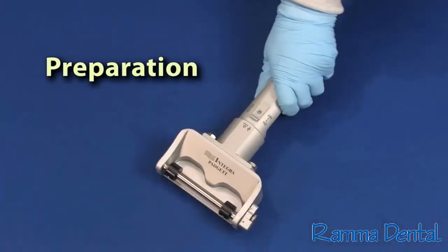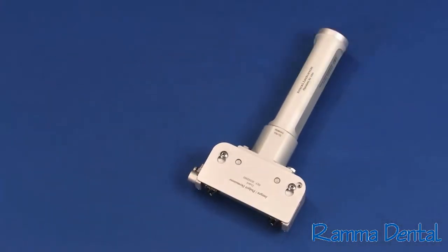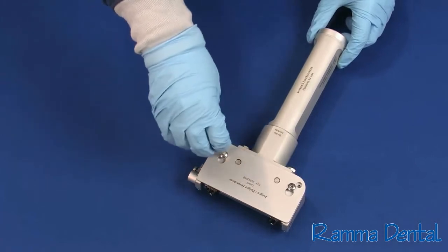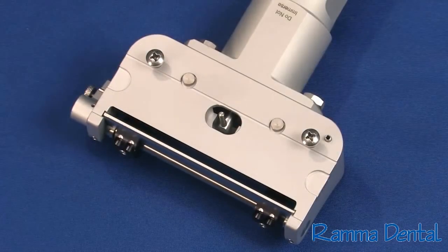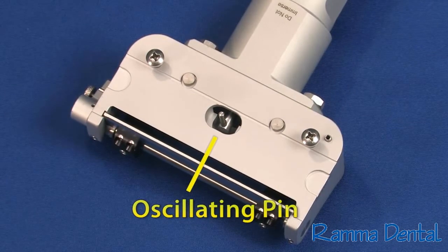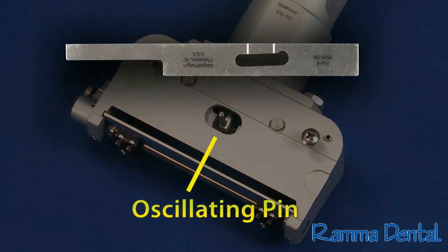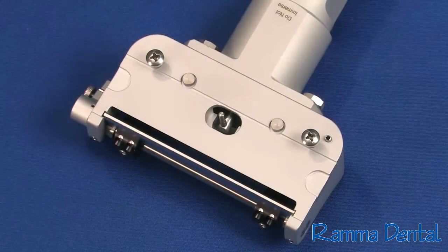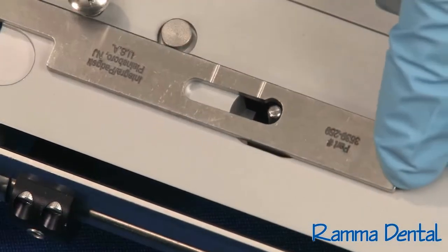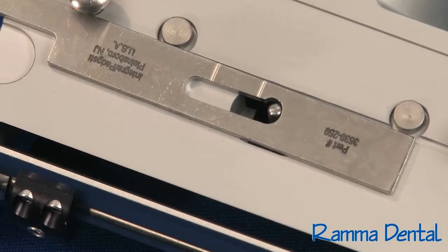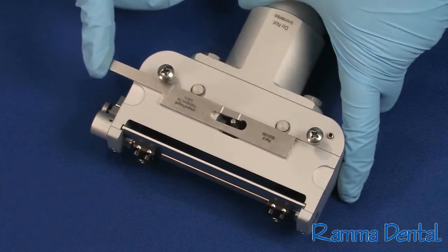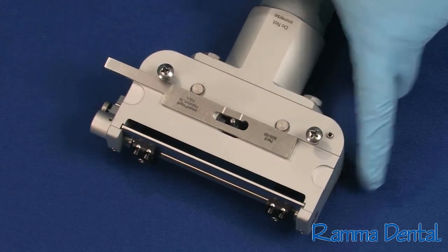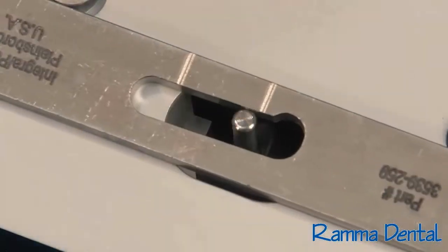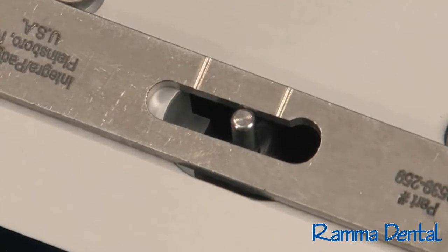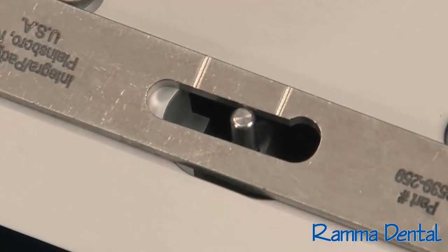To prepare the dermatome for use, first, remove the guard by loosening the screws and lifting it off. Before each use, it's important to check the pin position of the dermatome with this simple pin position guide. This determines if the oscillating pin is within specification to enable proper blade movement. Place the wide opening of the pin positioning guide over the oscillating pin like this. Lightly push on the side of the gauge with your right index finger, allowing the gauge to slide into place. The spring tension in the oscillating pin creates friction, which stops the gauge and allows for an accurate reading.